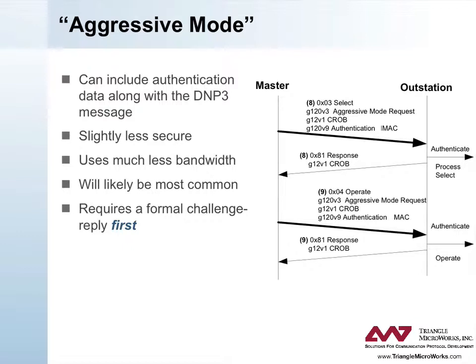Aggressive mode must be supported by all DNP3 secure authentication implementations and will likely be very commonly used. However, it cannot be used exclusively. Before it can be used, the two devices must first perform a challenge-reply sequence. This is required so that the master has the appropriate pseudo-random data in order to calculate the MAC. This does not provide an equal level of replay protection to a complete challenge-reply, but it's still probably adequate while significantly reducing the amount of bandwidth required.